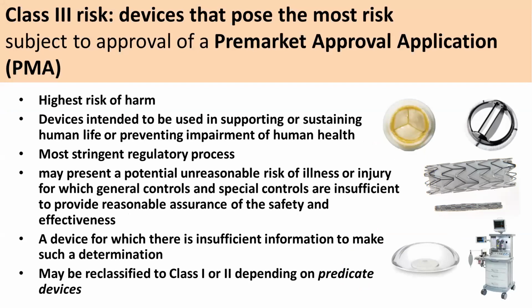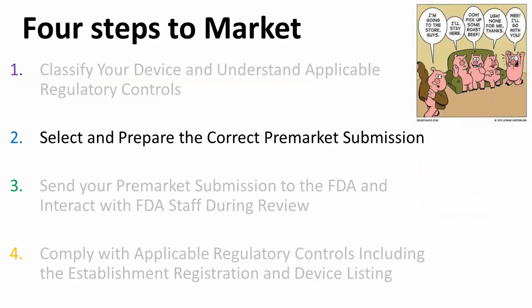Now, some devices that aren't that harmful might be a class 3 at first because there's just insufficient information to make a good determination. And so they might be reclassified to class 1 or 2 depending on predicate devices, which we'll discuss. But otherwise, these are devices that might have unreasonable risk of injury and need the most stringent regulatory process.